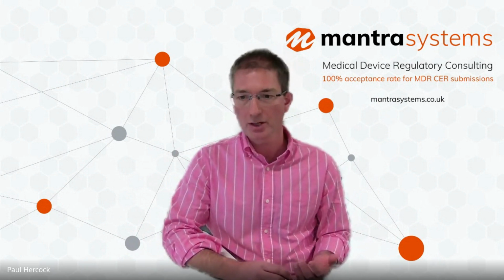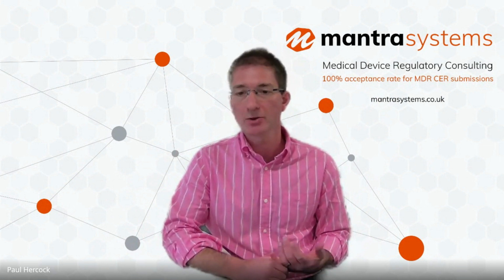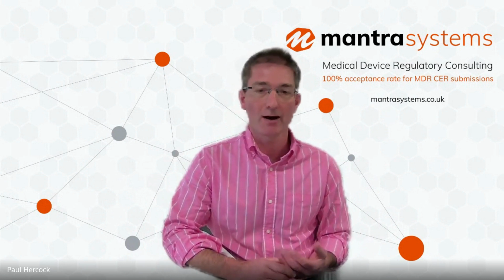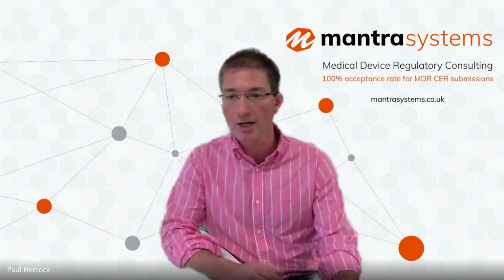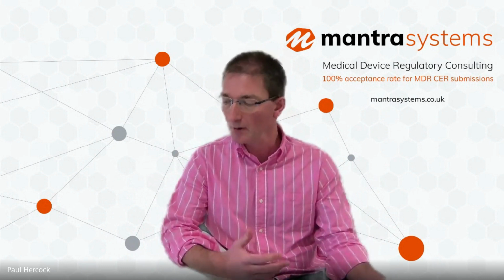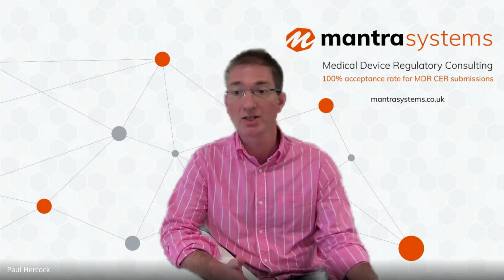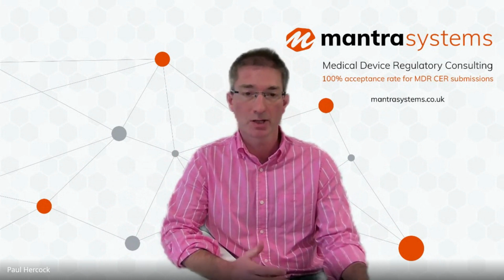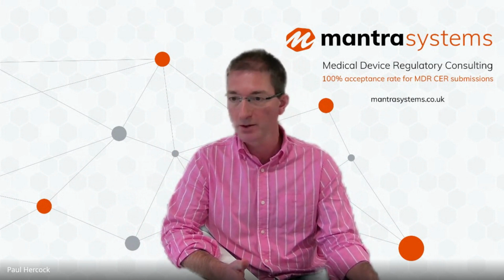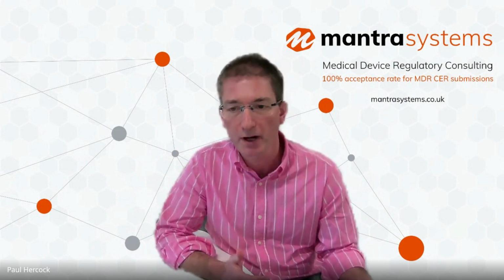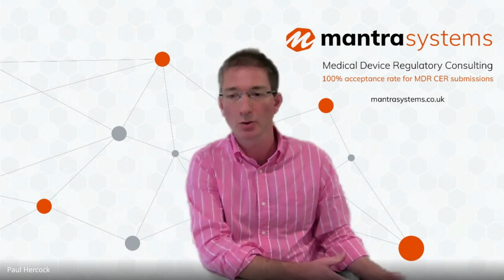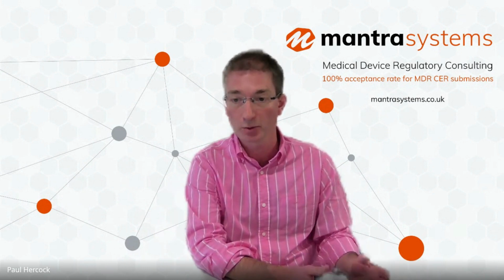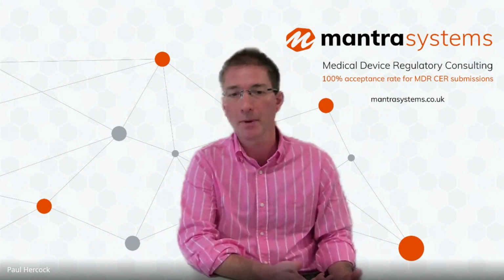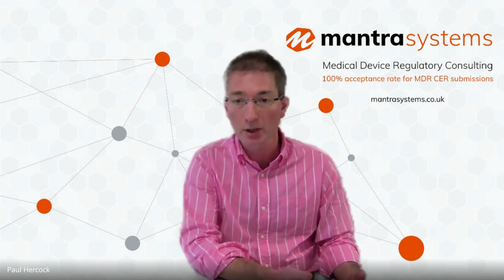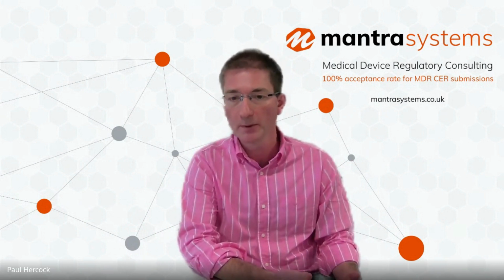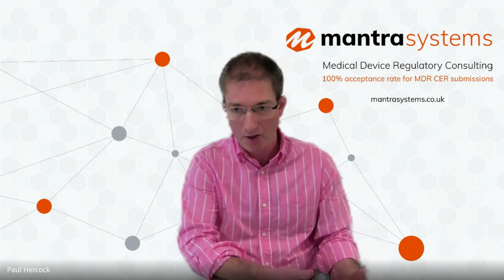There's several other rules to use Article 61(10). One is around the nature of the interaction with the human body. And so it needs to have a low risk and usually low duration interaction with the human body. It needs to be of a risk class that's not excluded from use of Article 61(10). So most class 3 devices are excluded from using that route. You need to justify why it's appropriate to use it. Again, really, that's all about the justifications as to why using clinical evidence would be inappropriate. And importantly, the manufacturer is not allowed to make any clinical claims of benefits or performance claims. So everything needs to be non-clinical.